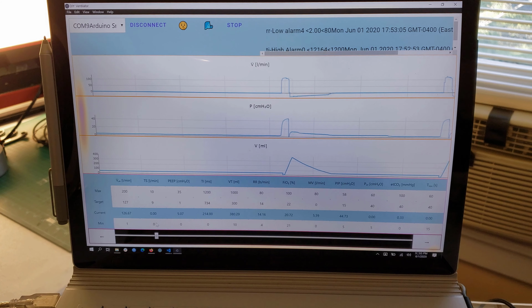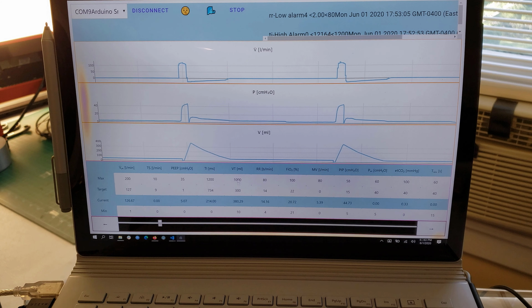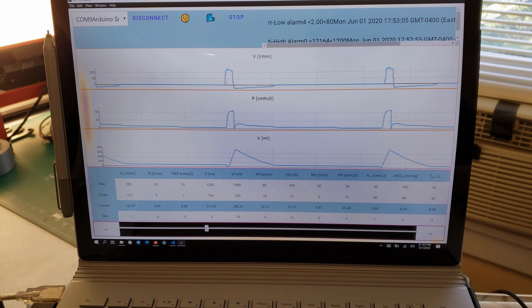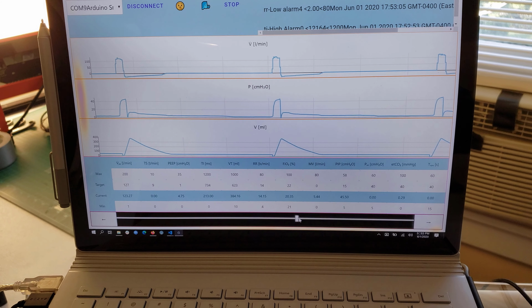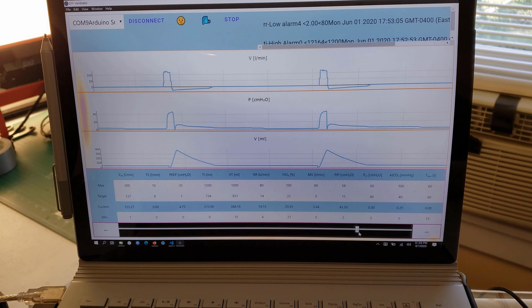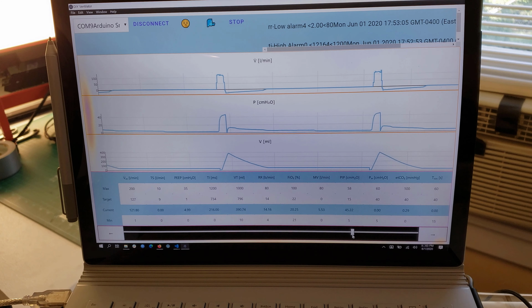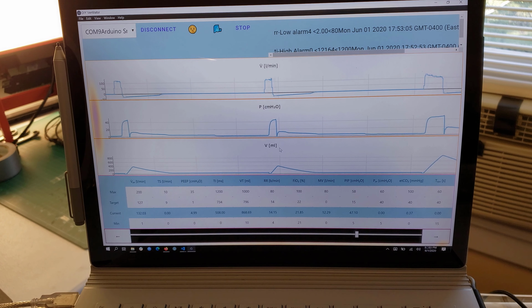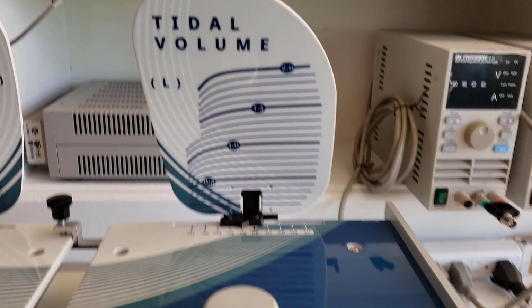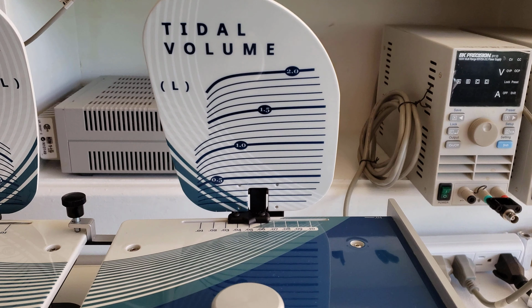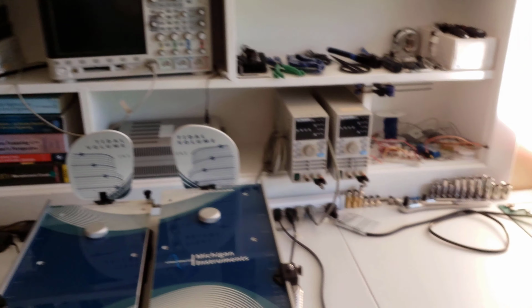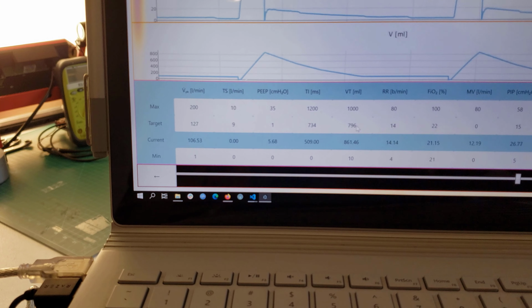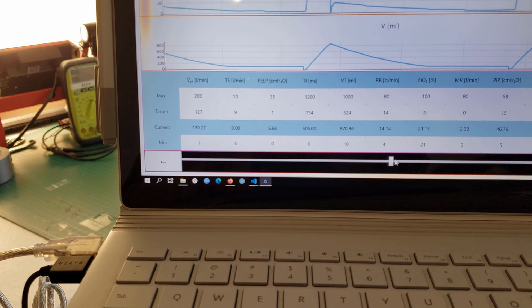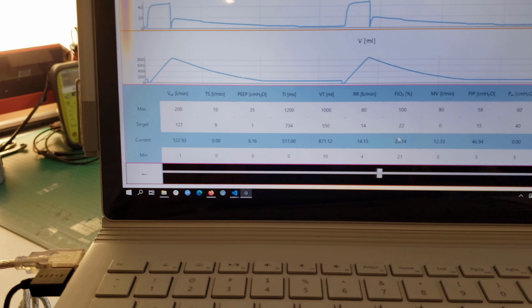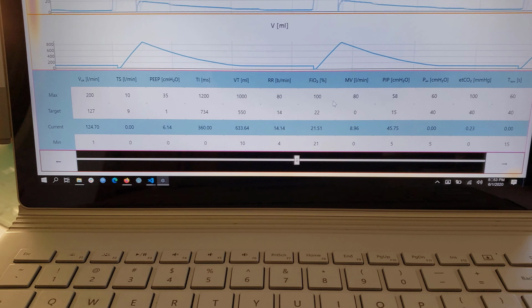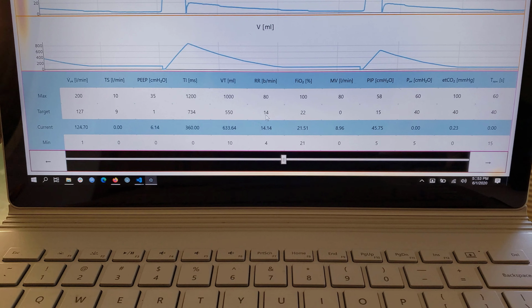There we go. Anyways, so next is tidal volume. We can set that to be higher. We can go up to 800, which is crazy high for a 7-foot man. We can achieve that. There it goes. And you can also see here that we're getting up to 800 on the Michigan Instruments lung simulator. And then I'm going to go back down to a more reasonable 550. That's what it would take to inflate my lungs. I'm a 5'8" man. And then skipping RR.